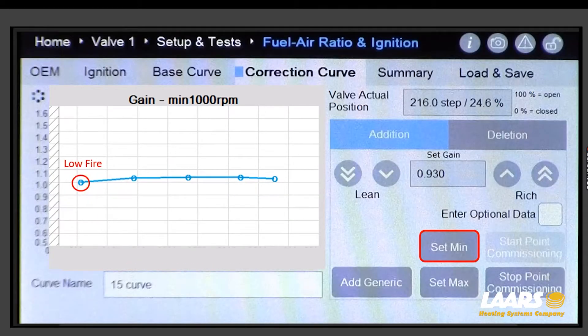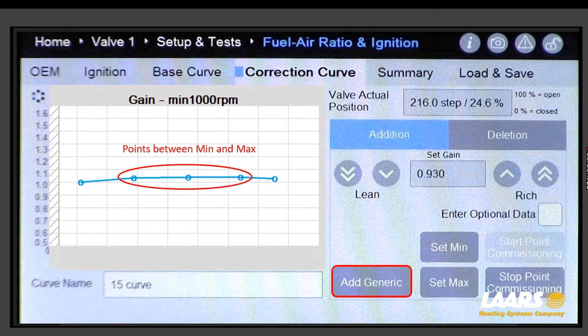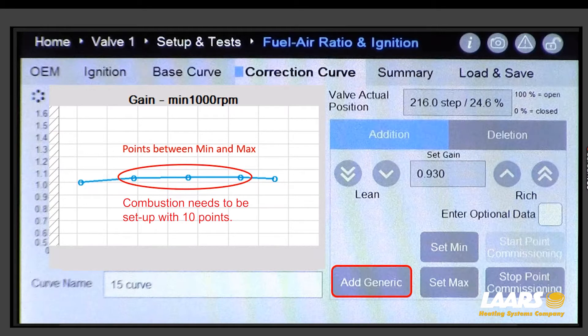Your first point is low fire or set min fire. Your last point is high fire or set max fire. The points in between are generic points. We'll check combustion or CO2 at each point — we want to see 10 points for combustion.